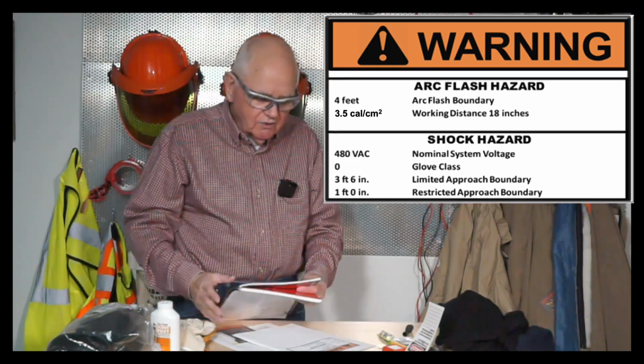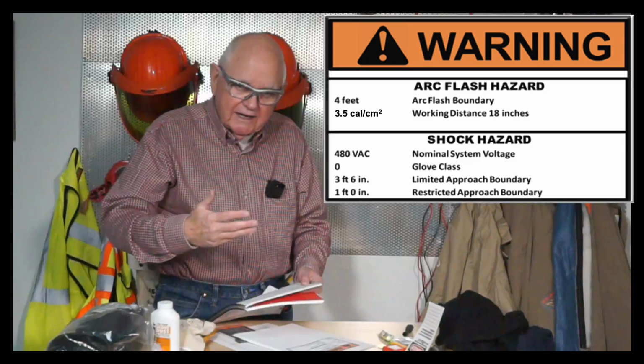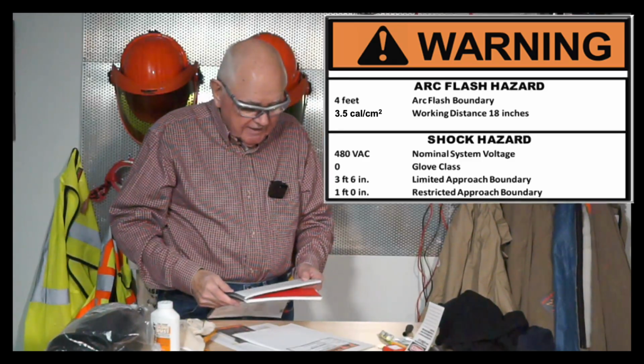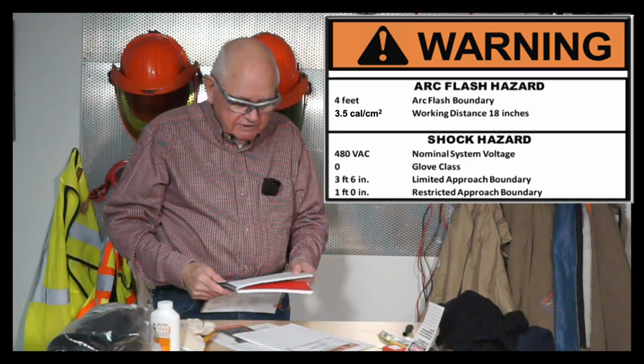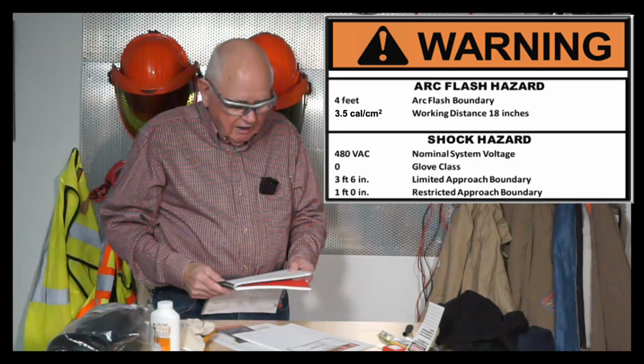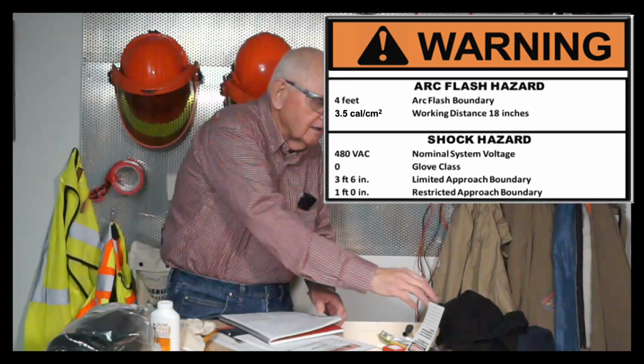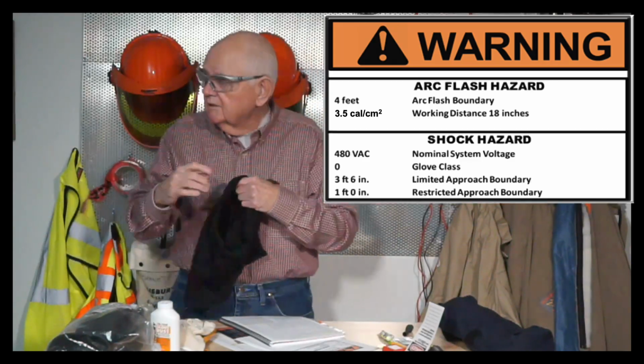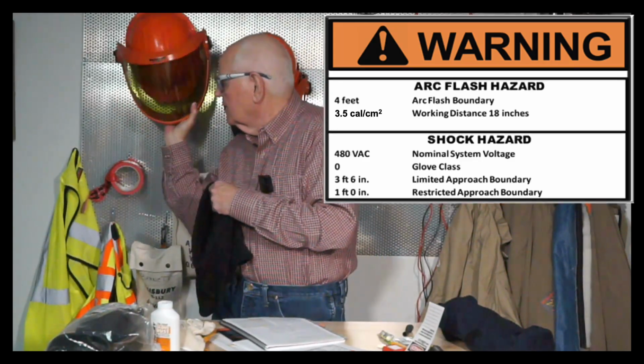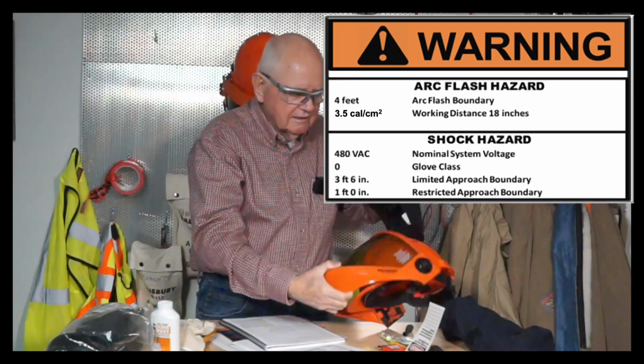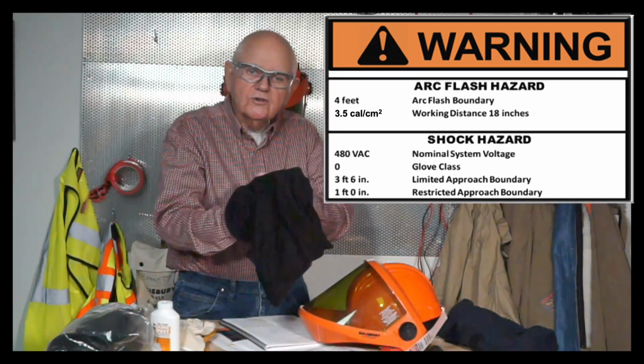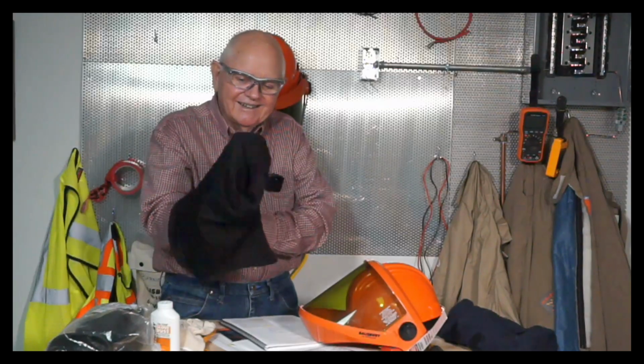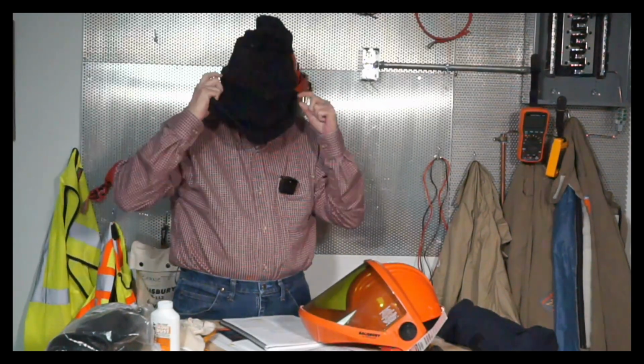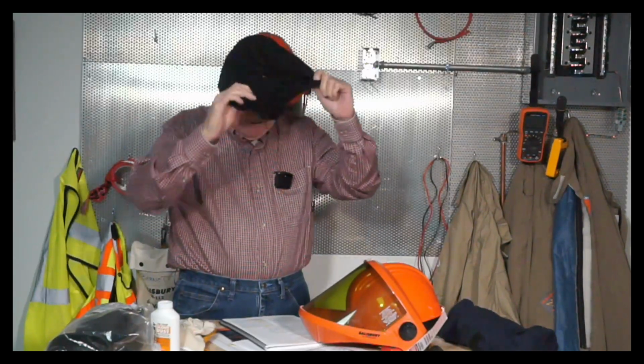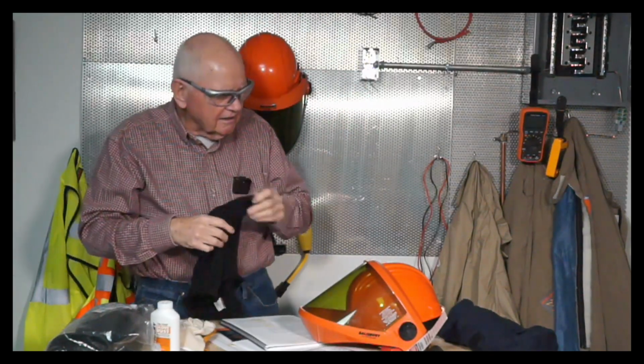So anyway, it goes through and tells me I have to wear arc-rated clothing with a rating at least equal to that 3.5 calories, long sleeve shirt and pants, or an arc flash suit, arc flash face shield, and an arc-rated balaclava. So I would need my face shield from up here and my balaclava, which is my sock hood, right? It's an older term that we've used, but it makes sense to me. Okay? And so I put this on, tuck it in, and that's going to give me the protection for my chin, neck, and so on.